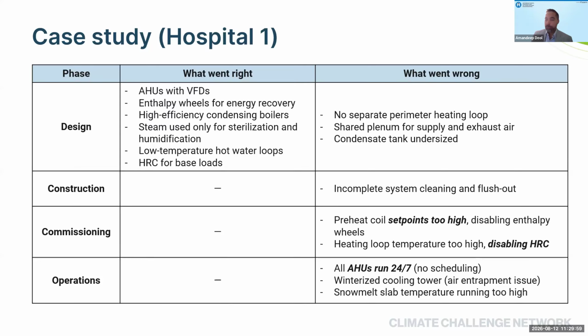But in the commissioning phase, the heat wheels, which were supposed to be set up to recover the ventilation exhaust energy, were set up incorrectly, and the set point was too high. It resulted in disabling those wheels, and that energy could not be recovered. Similarly, the heat recovery chiller, which is very sensitive equipment in a typical hospital configuration from an operations side, if not run at the proper temperature it is designed for, generally causes operational issues or results in inefficiency. In this scenario, the heating loop was operated too high, which basically disabled the heat recovery chiller. And without the heat recovery chiller, all the waste heat from a 24/7 load was basically rejected outside to the atmosphere instead of being used within the building.